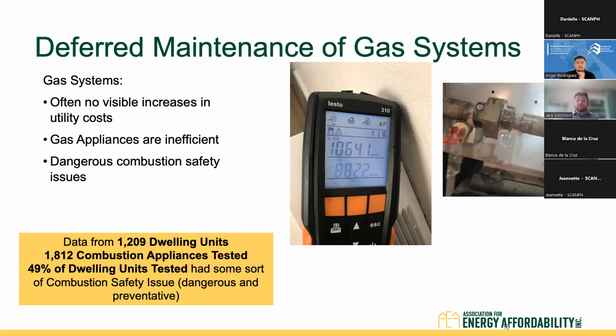In all of those programs, there's an aspect of combustion safety testing that we do. A few years ago, I decided to put together some data associated with that testing. From that analysis, we tested 1,209 dwelling units and 1,812 combustion appliances, and around 49%, close to 50%, of those units had some sort of combustion safety issue, either dangerous or preventative. When we're talking dangerous, we see some photos here on the right: high carbon monoxide in a wall furnace, and a gas leak on a pool boiler.